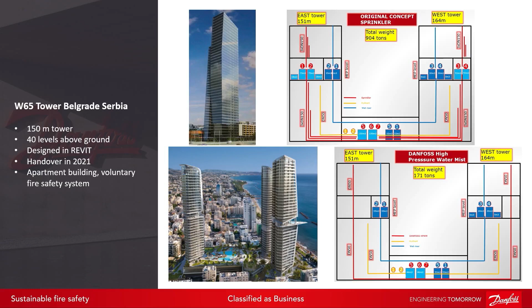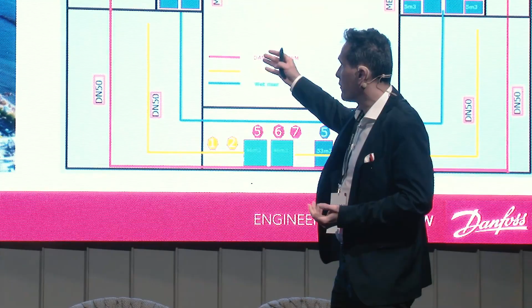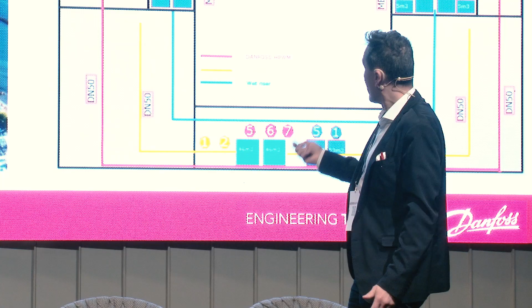Here is a picture, Belgrade, 155 meters. Interestingly, in Cyprus, this high-rise building, if you compare the two charts, the pointer isn't moving much, but you free up a lot of space for the tank, because at 155 or 200 meters high-rise you need an intermediate tank. You free up that area and make luxury apartments, you win money. So it's again about investment costs and ideas, and you have one riser instead of many different risers splitting the system.